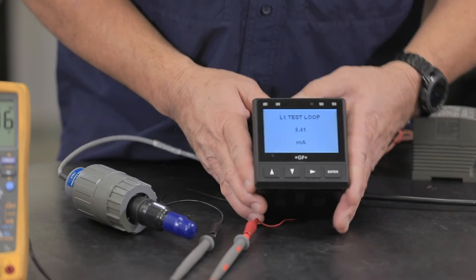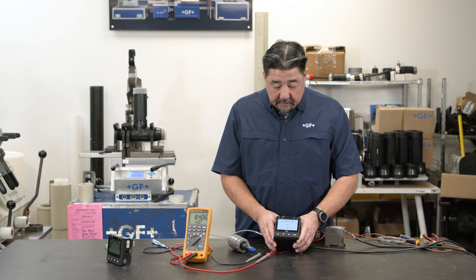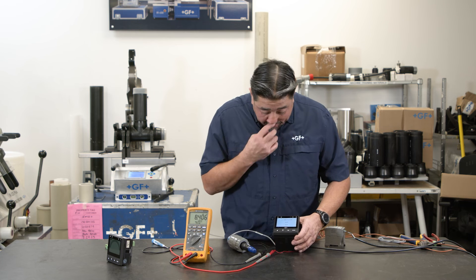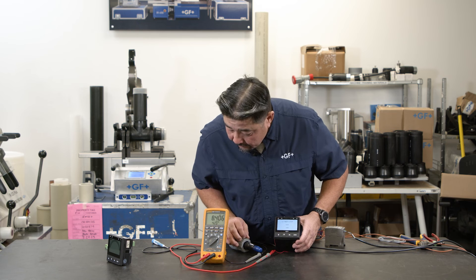Test loop. So actually the 9900 and the 9950 work as a signal generator, and we could generate 4 to 20 to test a unit. So right now 8.41. I should be showing 8.41 on my multimeter. Pretty good.